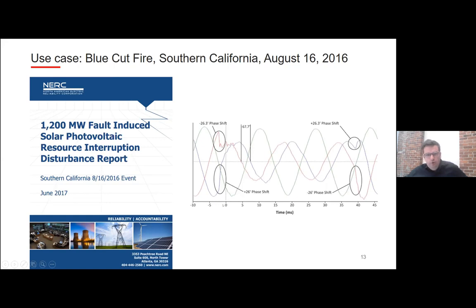Long story short, what actually happened is that the PLL of their solar inverters was poorly designed. A fault injected on the line when a tree fell caused a line-to-line fault, and line-to-line faults, from the voltage standpoint, look like phase-shifted sinusoids, and also the amplitude goes down.